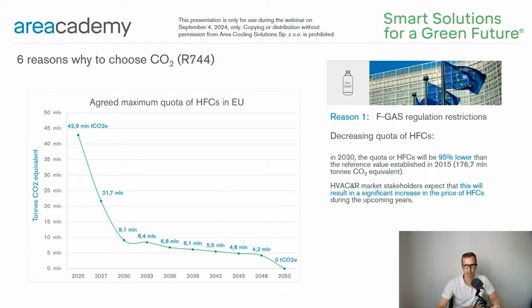Recently, the general trend is that the European refrigeration market is moving toward natural refrigerants. I want to present 6 reasons why using the CO2 in the refrigeration installation is worth considering. The first and most impactful reason for this shift is the European F-gas regulation, which was revised and updated at the beginning of this year. It is a crucial driver in the transition towards natural refrigerants.